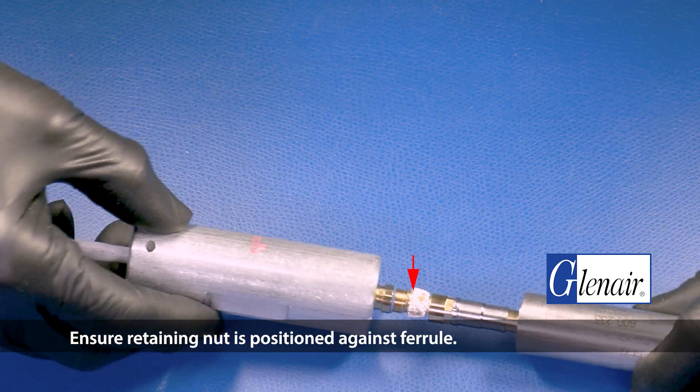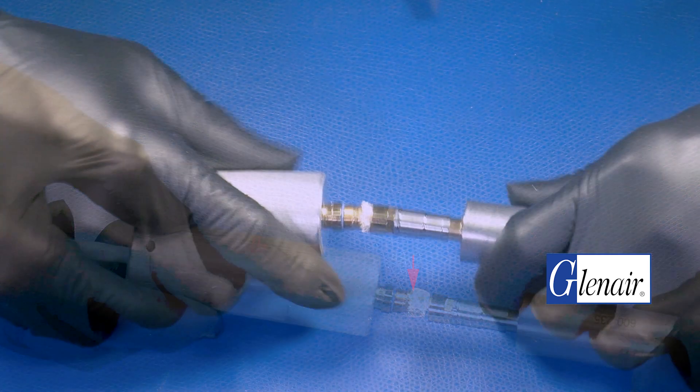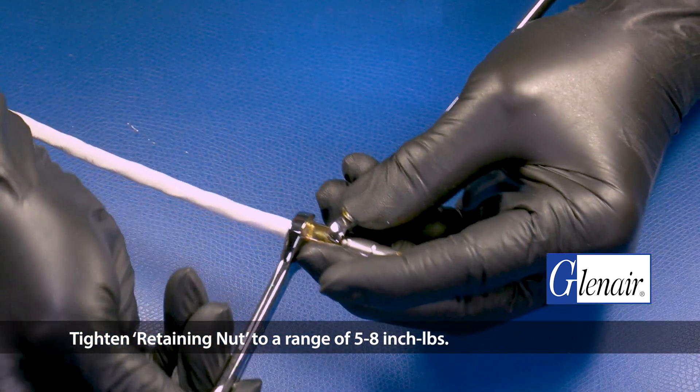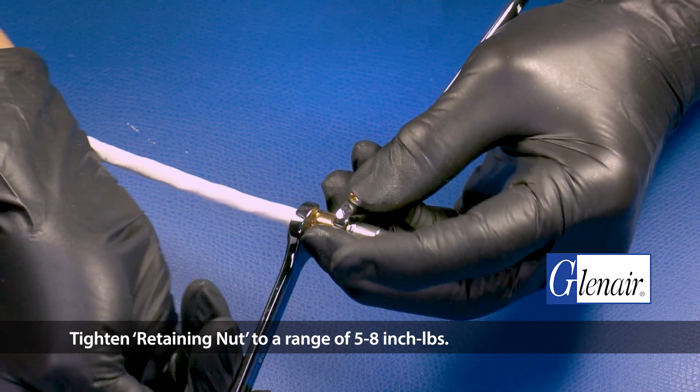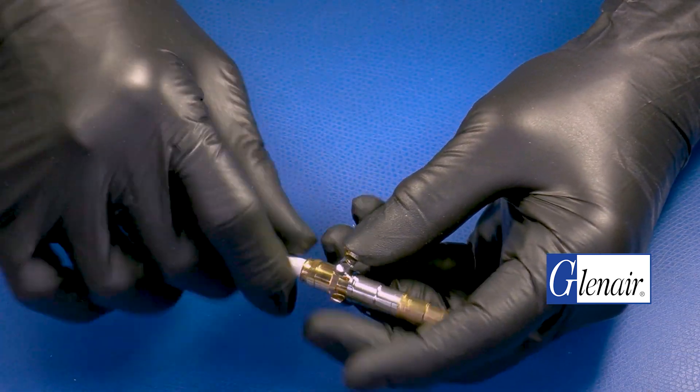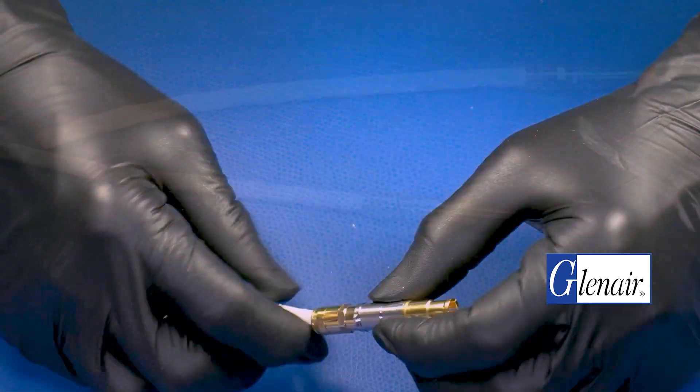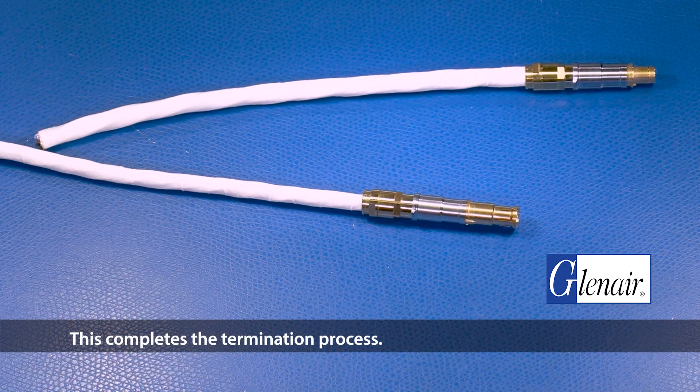Ensure retaining nut is positioned against ferrule. Press contact assembly into outer body housing. Tighten retaining nut to a range of 5 to 8 inch pounds. This completes the termination process.